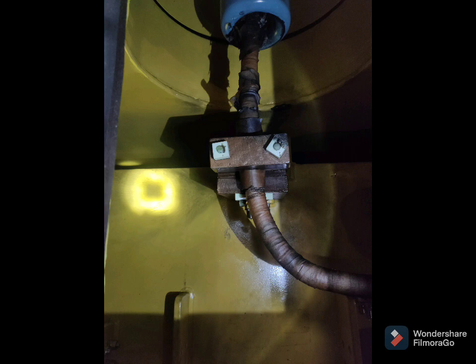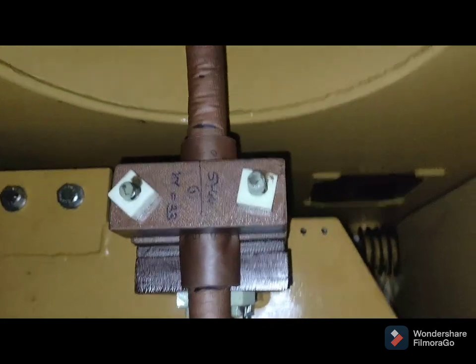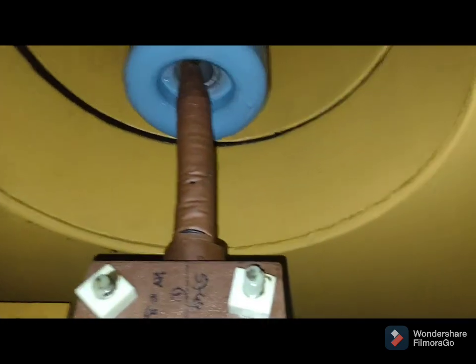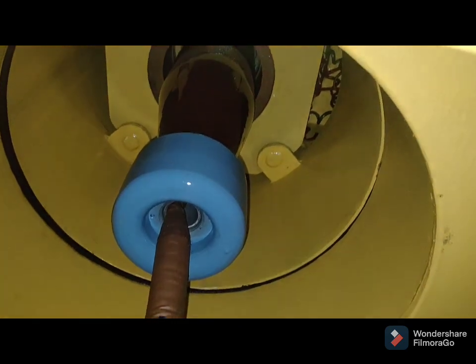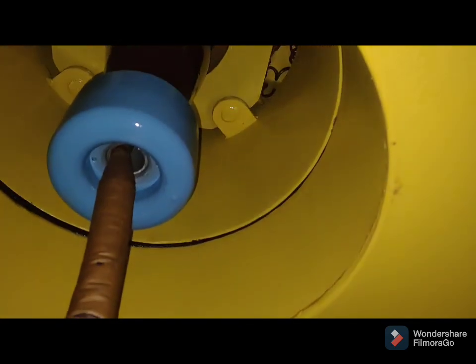Now I am showing one fresh lead and one damaged lead — this is the damaged lead and damaged epoxy. Now I am showing you for reference the good epoxy and good lead of the bushings. You are seeing the good epoxy and good leads of the HV portions.